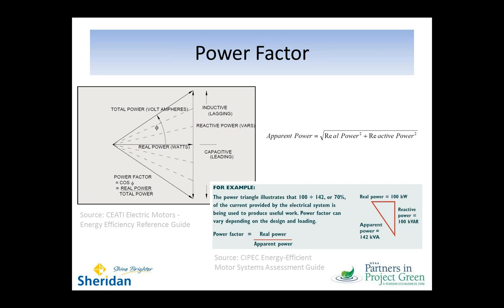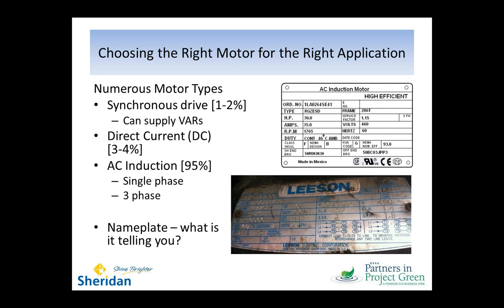So your induction motors in your facility are going to significantly lower power factor, and your utility is paying attention to that and will often levy a penalty if it sees power factors drop below 90 or 95% in your facility. So they're definitely watching that.